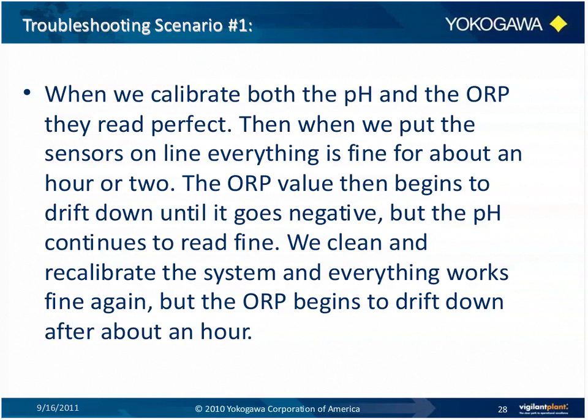However, if this solved the problem, this would mean that you could not, in that particular application and installation, measure pH and ORP with the same electrode. You would have to have two different installations.